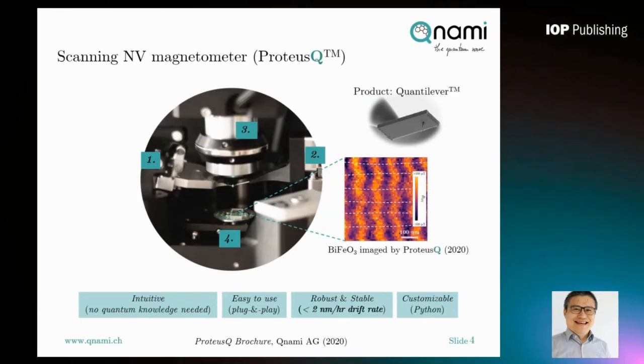Qnami ProteusQ has a few key advantages. First, it is very intuitive — you only need a little knowledge of quantum mechanics about the NV center, and it is very easy to use. We designed the system on a plug-and-play principle; you can put in your sample and directly start measurement. Most importantly, it is very robust and stable — the thermal drift rate is smaller than 2 nanometers per hour over a course of 2 days. Finally, it is customizable: the software is programmed using Python, so customers can develop advanced applications by programming themselves.